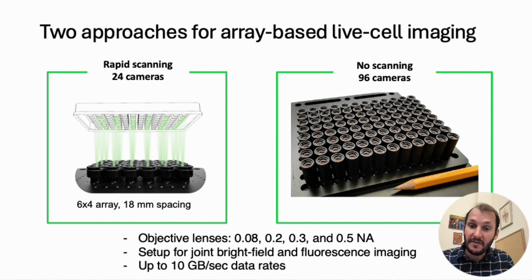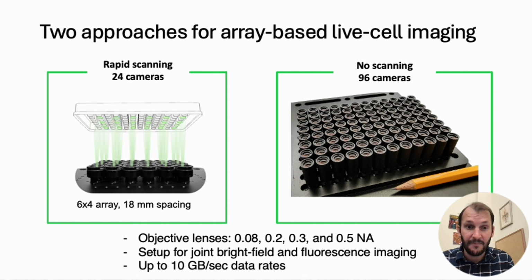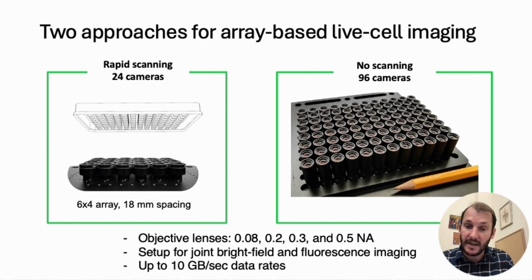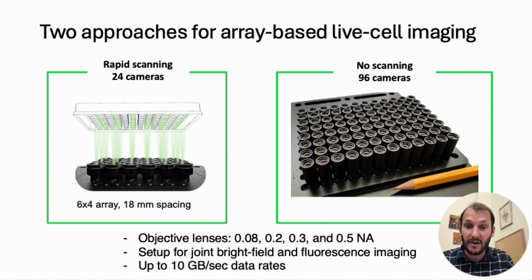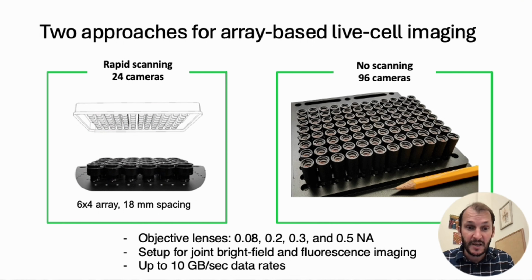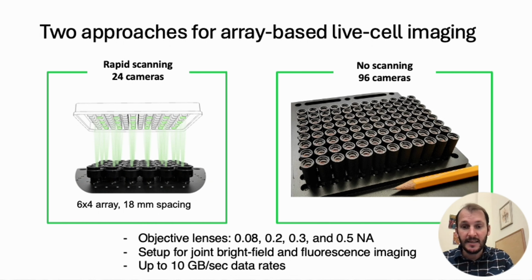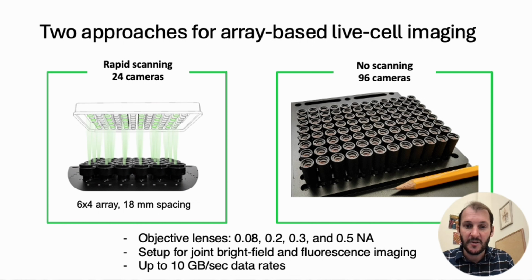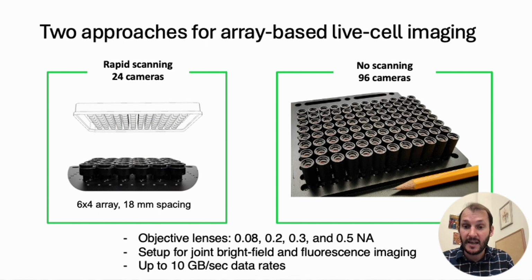We've developed two different approaches to this higher resolution imaging modality. One contains 24 cameras, and we can image all in parallel, just like the previous MCAM design. And to image a 96 well plate, we scan a little bit in a 2x2 grid.